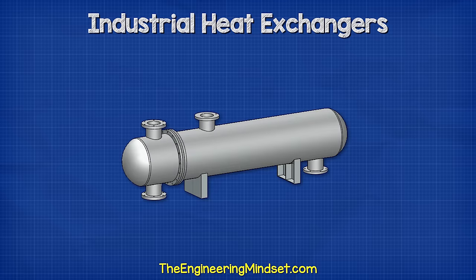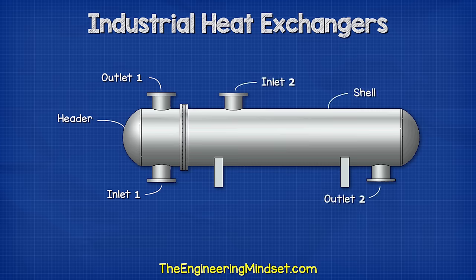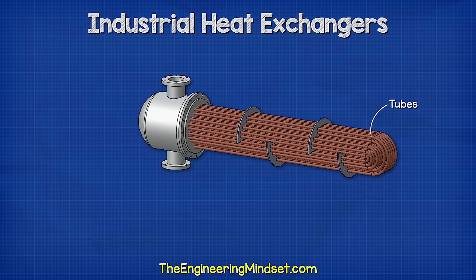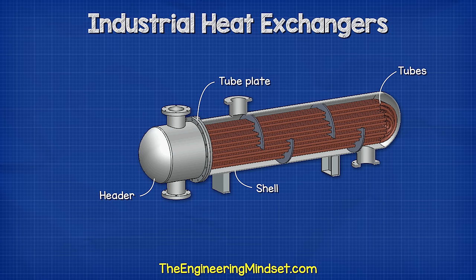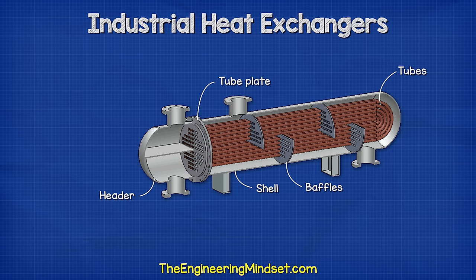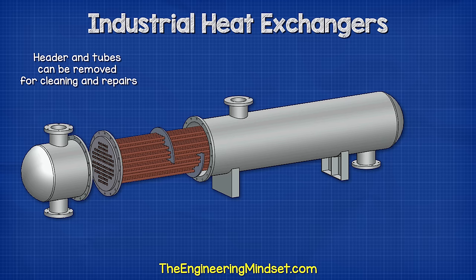Shell and tube heat exchangers look something like this. With this design, we normally find the inlet and outlet for one fluid at the very end of the heat exchanger, known as the header. Then we have another inlet and outlet for the second fluid on the main body, known as the shell. Inside the unit we have the tubes, which bend and loop around to start and finish at the tube plate, which sits between the shell and the header. The tubes usually also pass through baffles, which are sheets of metal. The header and tubes can be removed for cleaning, repairs, and maintenance.